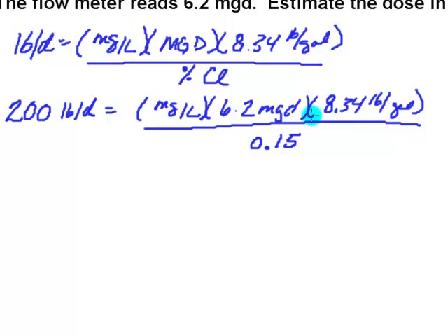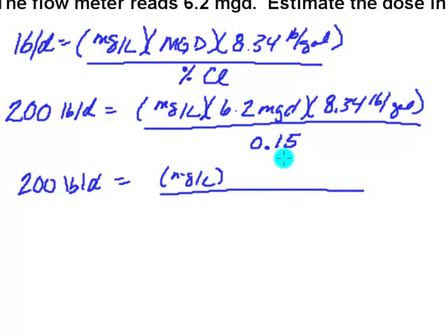So let's just bring down this side, 200 pounds per day. And I'm going to still have my milligrams per liter, but I can multiply those two things on the top. So I'm going to take my 6.2 and multiply it by 8.34, and I find that is equal to 51.708. I'm going to divide that by 0.15.